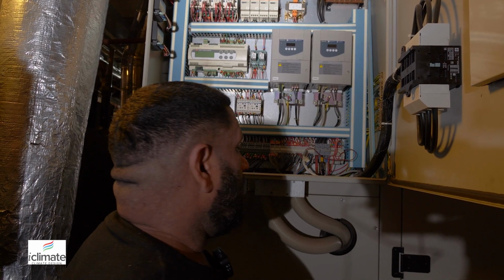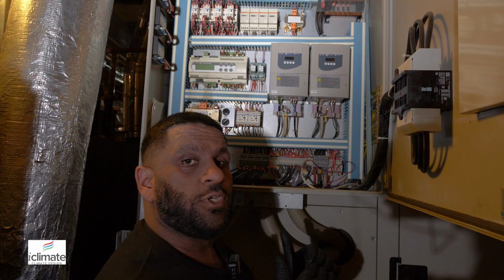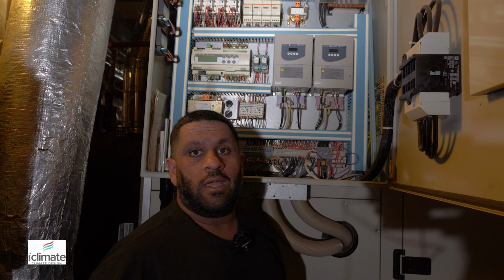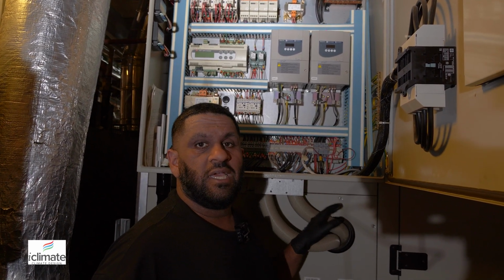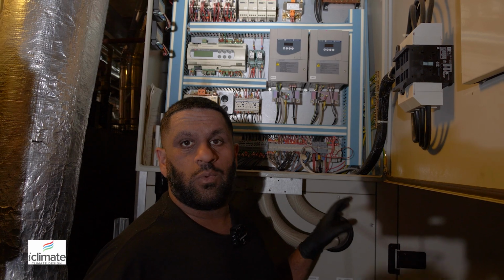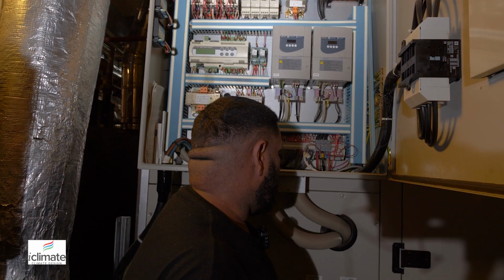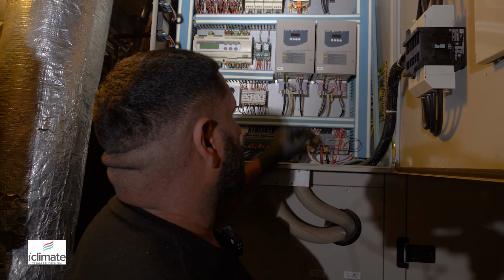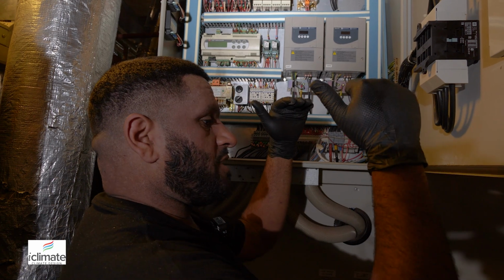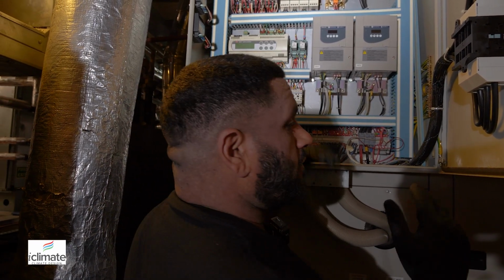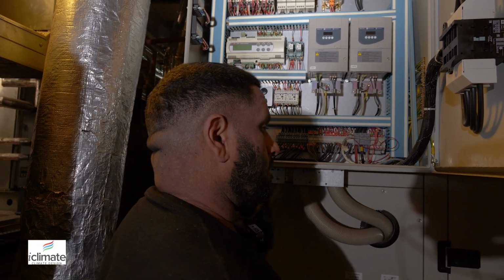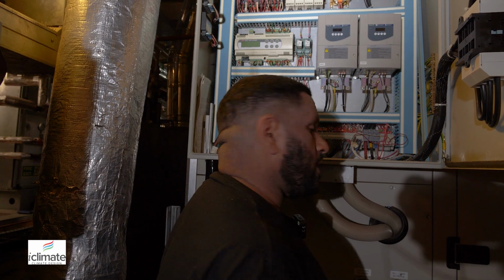Step 2 brings in, and then this will start at low speed on step 2 until it finds a sweet spot and it can regulate the water temperature coming through the evaporator here according to what's needed in the building. So if the building needs this to be at 100% capacity, this will generate 142 kilowatts of cooling capacity when both steps, both circuits, both compressors and both inverters are 100% ramped, with both expansion valve drivers all open. And obviously, 142 kilowatts at this age, it needs to be maintained properly.